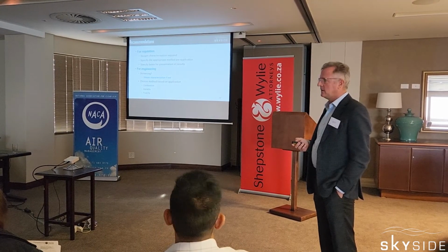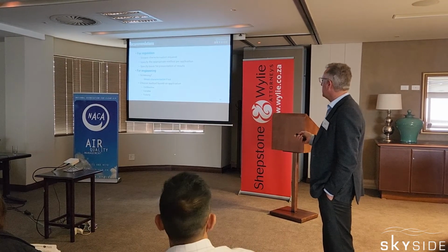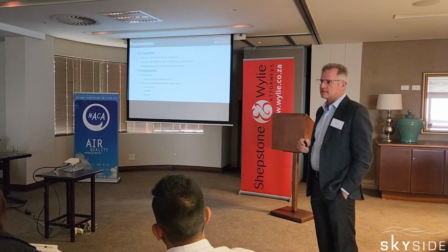In certain situations, for instance, NDIR, probably the cheapest method to apply, still gives you some sort of understanding of the variability of cycles if it's applicable for the compounds that are present. And then also specify the basis for the presentation, wet or dry, calibrated against methane or propane, for instance.